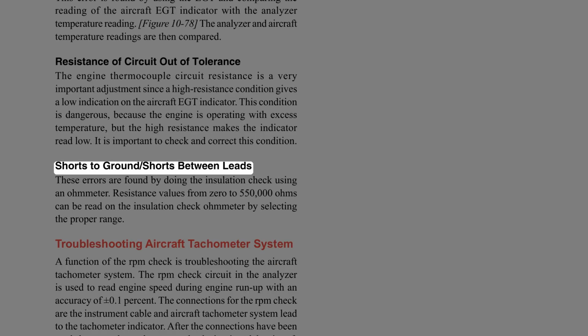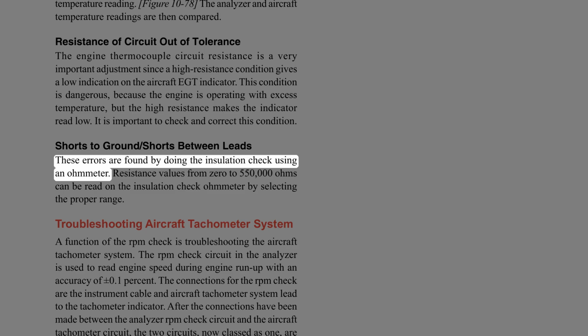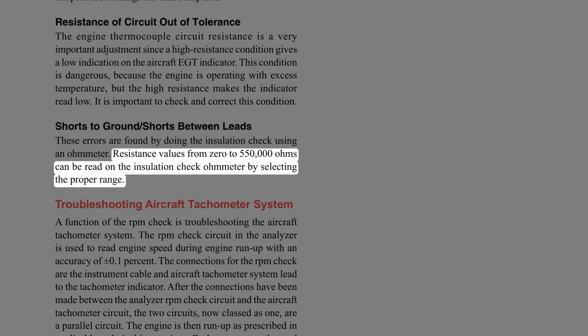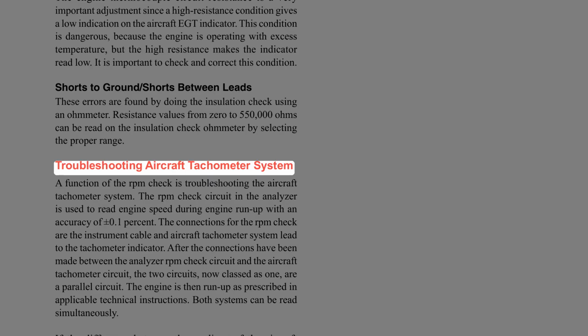Shorts to ground, shorts between leads. These errors are found by doing the insulation check using an ohm meter. Resistance values from 0 to 550,000 ohms can be read on the insulation check ohm meter by selecting the proper range.